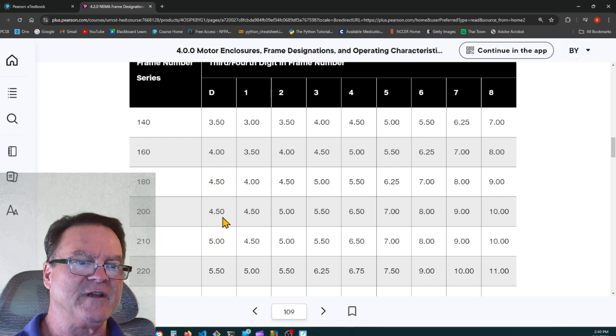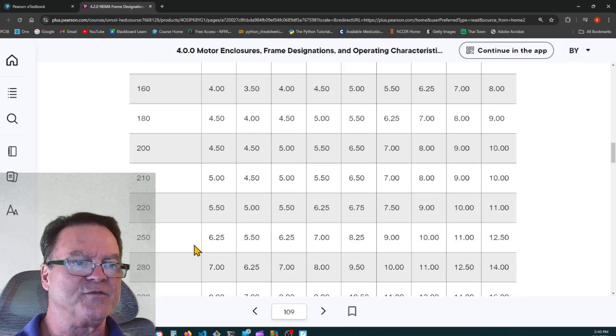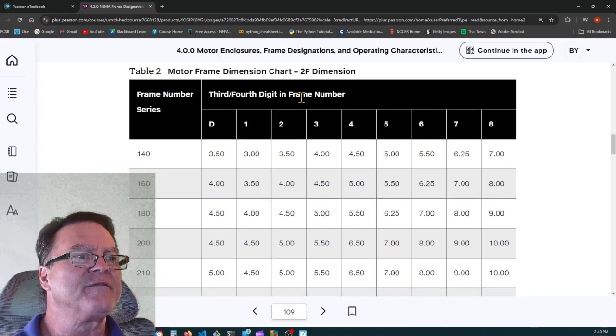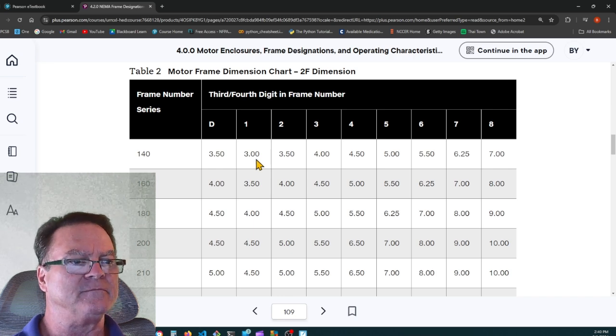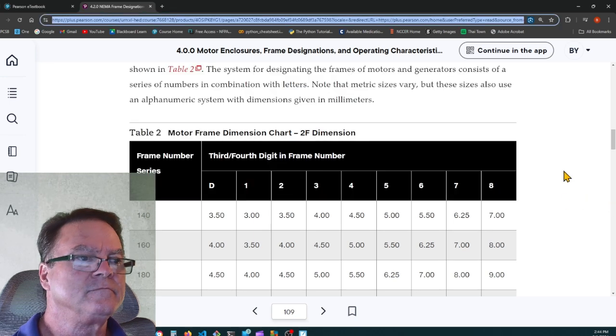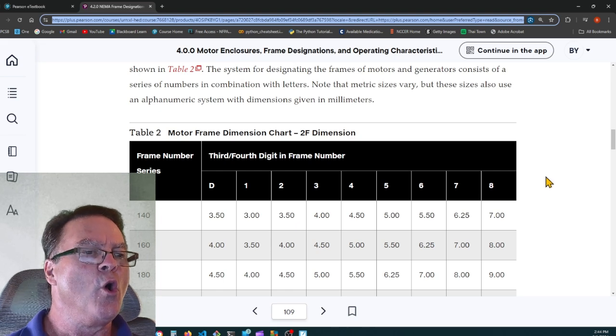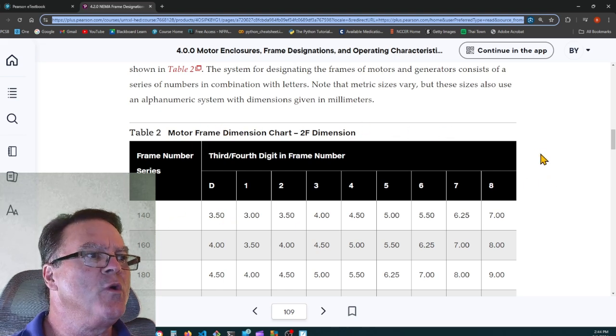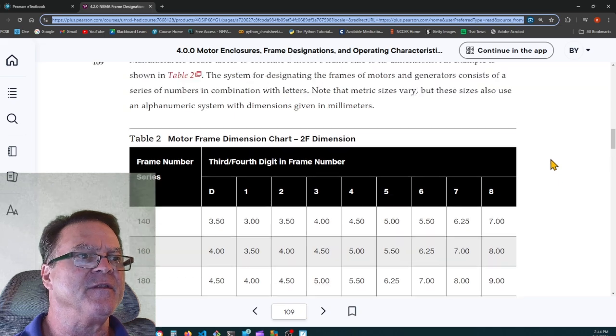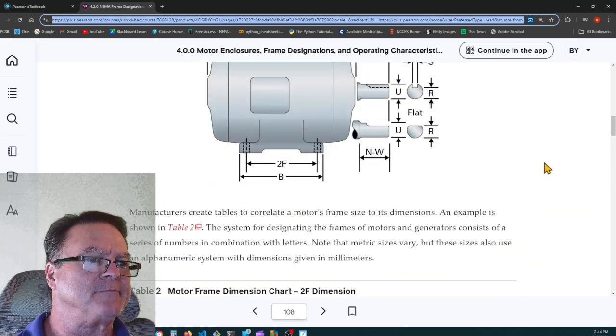See, this should be 5 inches. I don't know why they have it there as 200. 210 is 5, 220 is 5.5. 250 is 6.25 inches. And then the third and fourth digits in the frame number will actually increase that number. All right, so the first two numbers in the frame size.